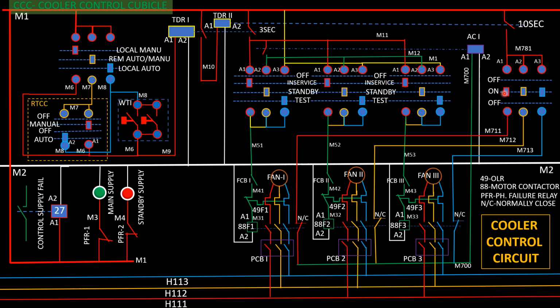When the temperature indicator pointer reaches a preset value, the contact of the mercury switch will be made here and all fans connected here will start after 3 seconds, which is controlled by TDR1. Out of 3, you can keep any of the fans as standby. Suppose the first 2 fans are kept at in-service mode and the third fan is kept at standby mode. In that case, if any of the first 2 fans kept in service does not run due to some problem, the third standby fan will start after a few seconds.